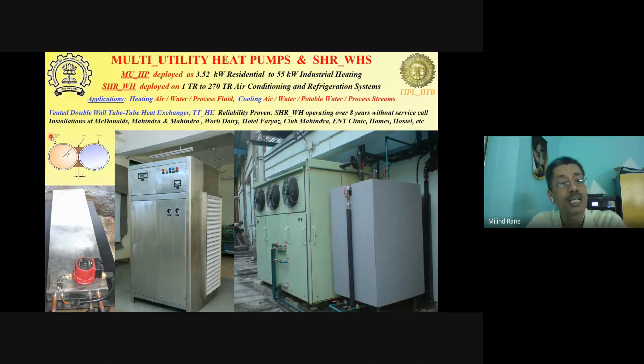So we developed a superheat recovery unit using our tube heat exchanger patent, where multiple tubes are put side by side, and one of the working fluids, that is the refrigerant, passes through one set of tubes, and the water to be heated passes through the other set of tubes. Now, because it is a double wall vented design, the chance of mixing of the refrigerant and the water is very, very remote. And because of this, this heat exchanger becomes very reliable. So as I said, we have had systems operating for over 11 years without a single service call in a hotel, generating 12 to 24,000 liters of hot water per day. So these are some of the systems that I just shared with you. Now, there are many applications. It could be used for heating of air, heating of water.